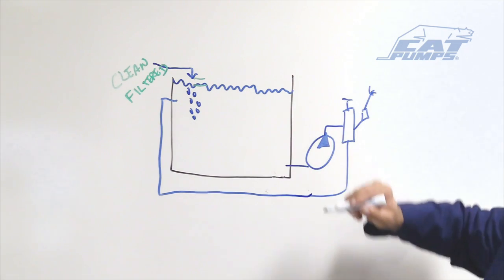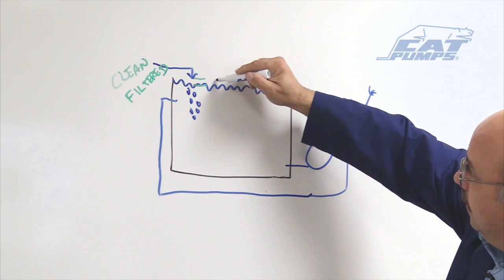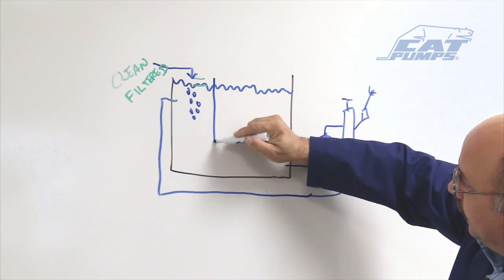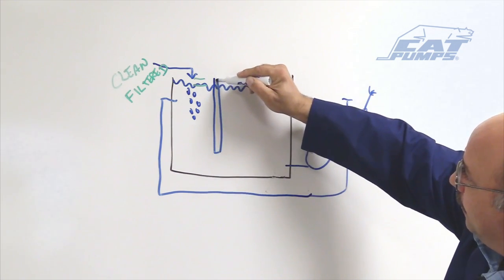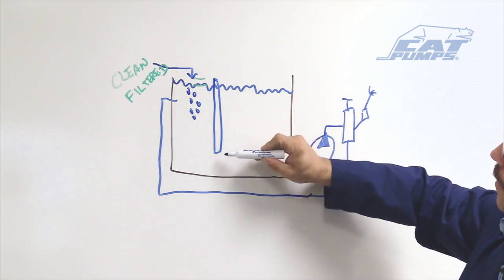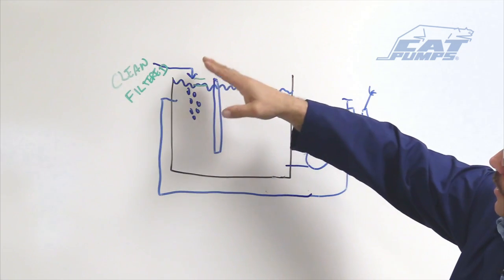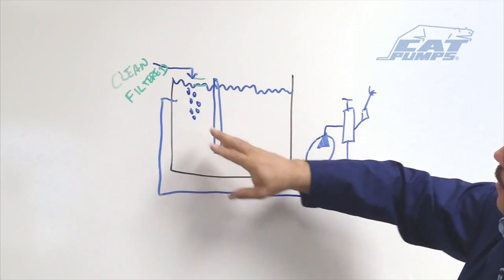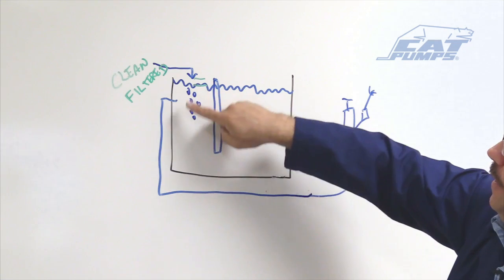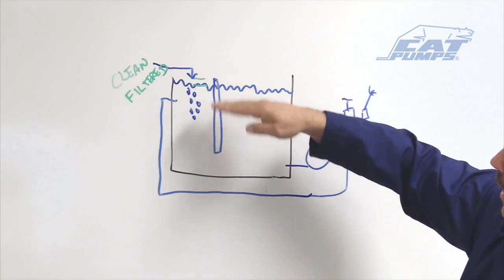So the first thing we can do is we can add a baffle right here on this side of the tank. And I'm going to put it above the water level but not quite to the bottom of the tank, because I want the water from this section to flow under that baffle. That way these air bubbles are trapped in this portion of the tank and they can be dissipated out.